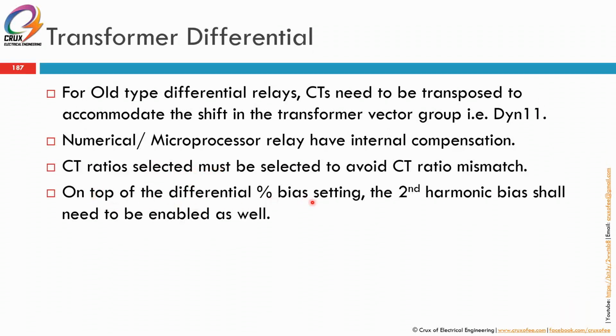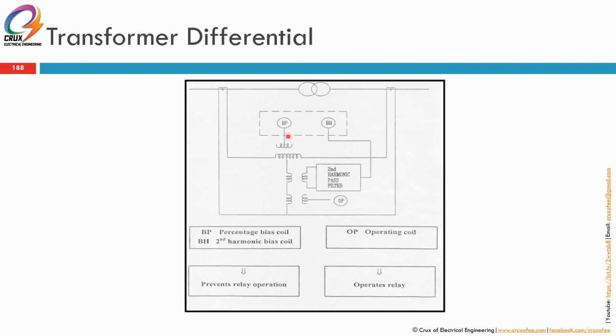On top of the differential percent bias setting, the second harmonic bias shall need to be enabled as well. This is for the transformer inrush during the energization of the transformer. So here's a differential relay with a percentage bias coil as well as a second harmonic filter coil. When there's inrush, this second harmonic pass filter coil will block or limit the current flowing through the operating coil. Same for the percentage bias. So these two will stabilize the transformer differential so as not to trip nuisancely.